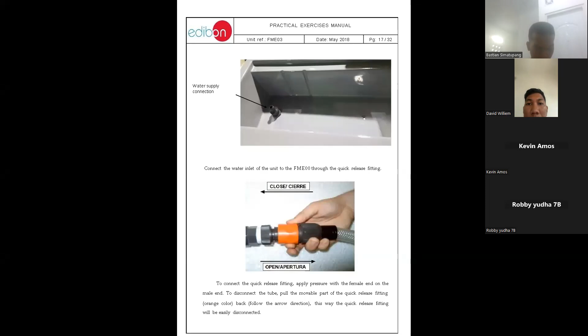Flow measurement with the FME00 unit. Procedure to measure the flow. Number 1, check that the VCC-1 valve is open. Number 2, check that the inlet and outlet connections of the unit are dry. Number 3, plug the drain of the hydraulic bench tank with the drain valve actuator provided for the purpose. Number 4, switch on the pump with the on/off switch.